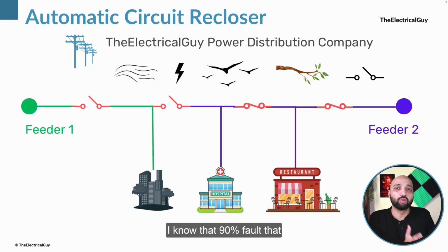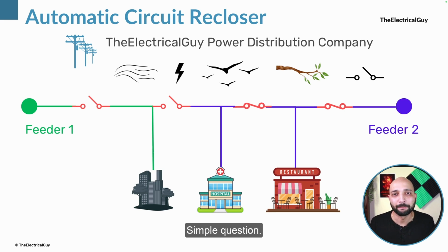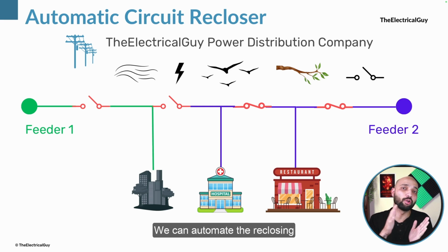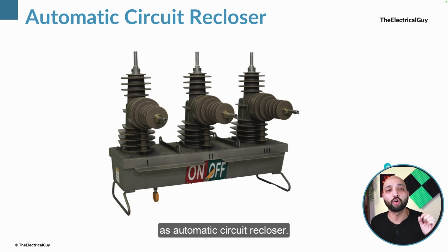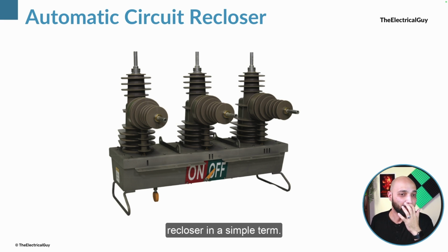Now, when I know that 90% of the faults that happen in my system are basically temporary in nature and will vanish automatically after a few seconds or milliseconds, can I automate this reclosing of the circuit breaker? Simple question. The answer is yes, it can be done. We can automate the reclosing of the circuit breaker, and that device is what we call an automatic circuit recloser. What you can see on your screen is the image of the recloser. In simple terms, what is this device?